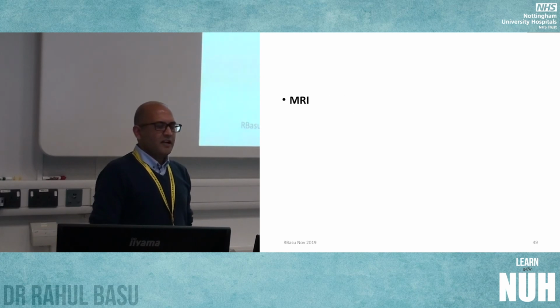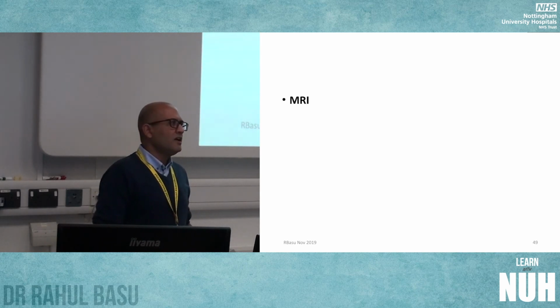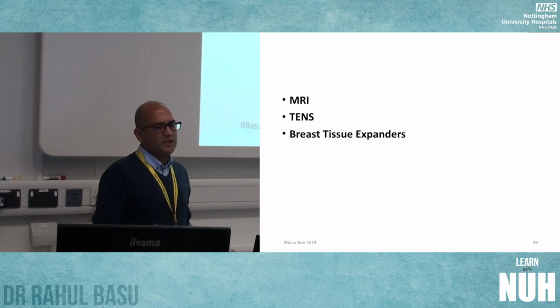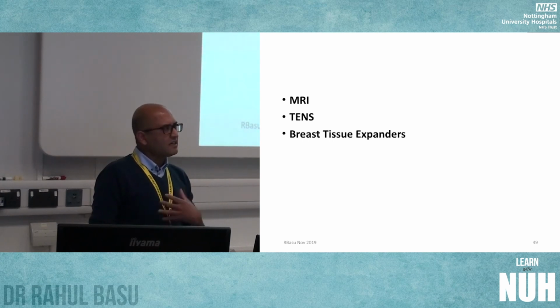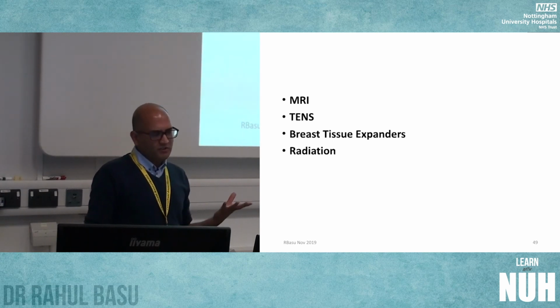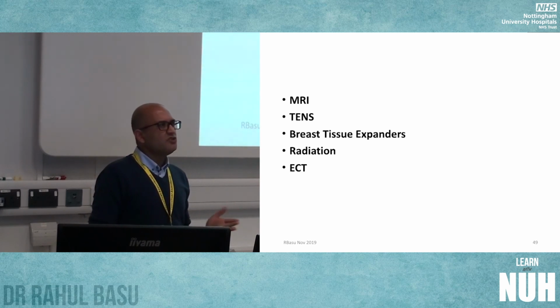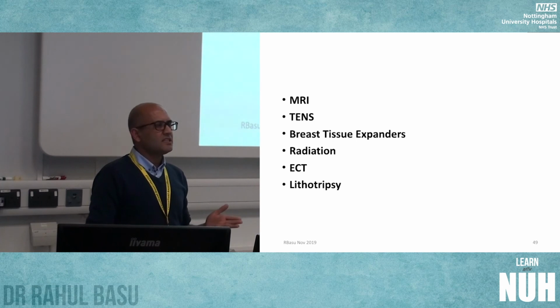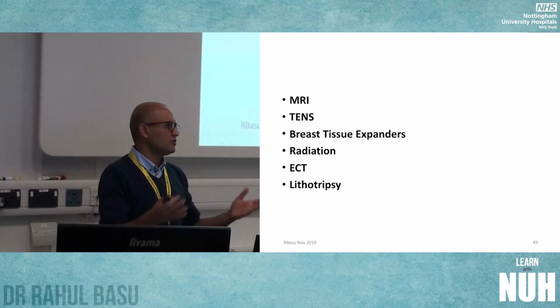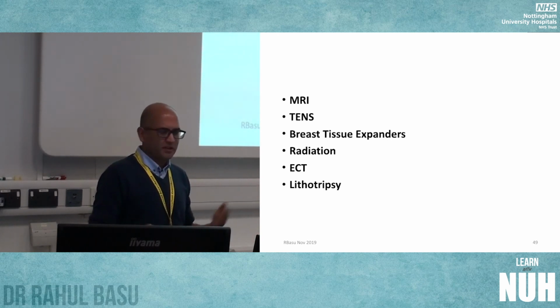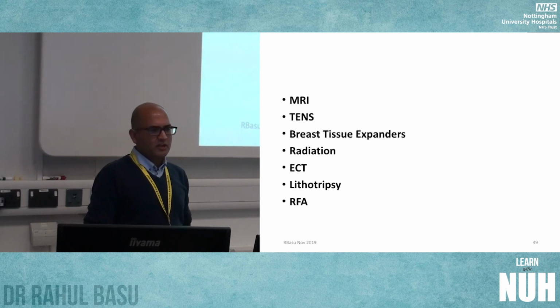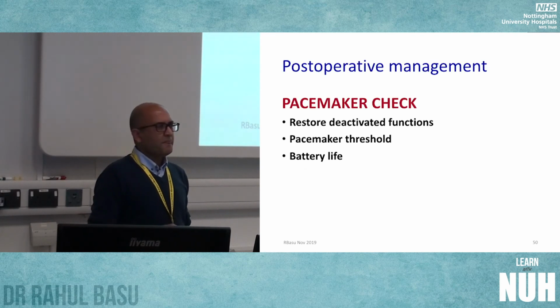I'm almost done. So main considerations: MRI and TENS. Both of these are contraindicated. There's some issue with breast tissue expanders because apparently they use a magnet to search for a needle, and that can interfere. Radiation can interfere, as I said before. ECT is usually safe, but they suggest after ECT and lithotripsy that you get the pacemaker box checked afterwards within a month, even if it's working properly. And radiofrequency ablation can interfere with pacing.